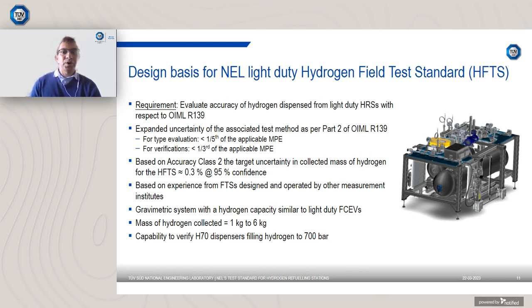And in part 2 of R139, you have the details on the expanded uncertainty that should be used for the associated test method. And for example, it states that for type evaluation, you need to have expanded uncertainty that is 1/5 of the applicable maximum permissible error. So based on this, if you have a class 2 accuracy requirement, then the target uncertainty for the field test standard is 0.3% at 95% confidence interval.